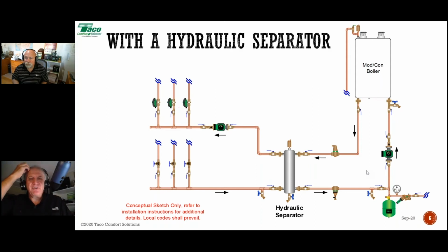So do you need both? I mean, if you really want to control air and eliminate air, then yeah. What's going to happen is anything that doesn't get back through the boiler is going to probably separate in that hydraulic separator, and you want to give it an option to get out of there. So it's not, well, if I have this, why do I need that? You kind of need both, because not all of the water from the system is necessarily going to go back to the boiler and through the scoop. So you're going to need both in that situation, I think.